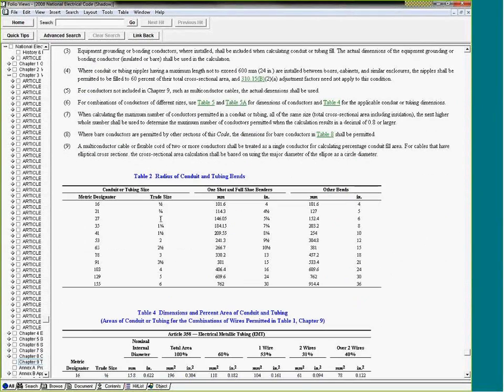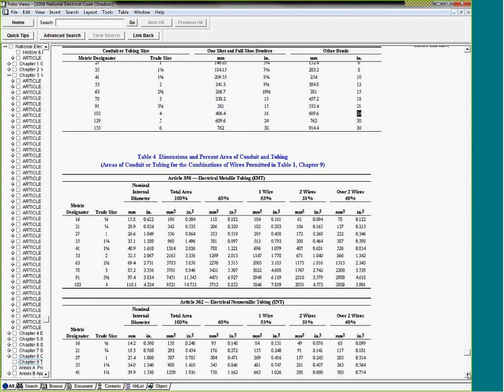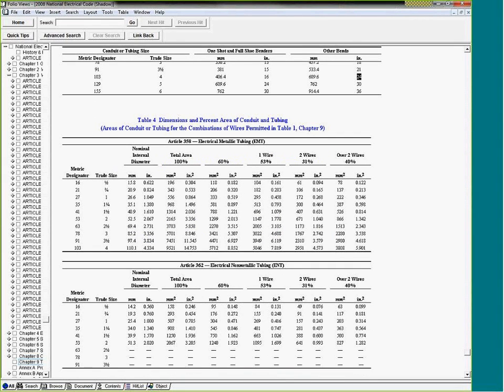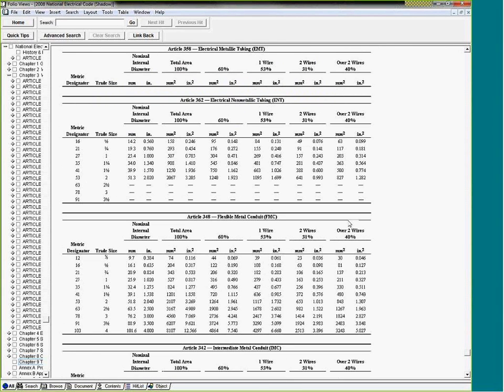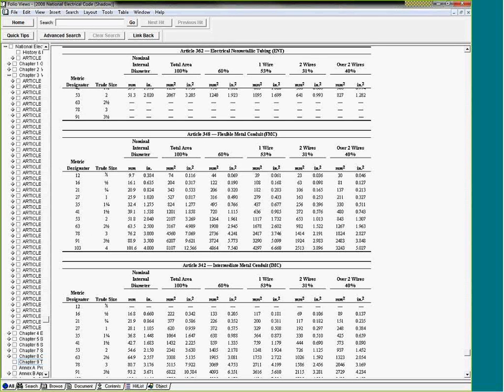Remember, guys, we kept talking about bending radius, and we said for flexible metallic conduit the minimum radius for other bends is 24 inches. Here are all the conduits, to do your calculation of how many conductors can fit in a conduit. I'm going to go to flexible metallic conduit. Here's my flexible metallic conduit, and I will bring to your attention, it starts only with 3/8 here. For the 3/8, we go to a different location.